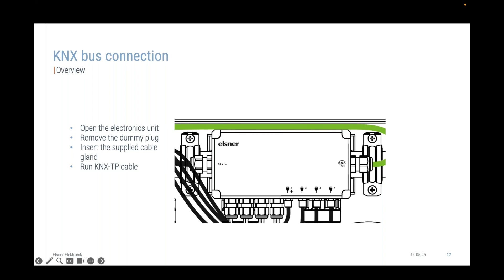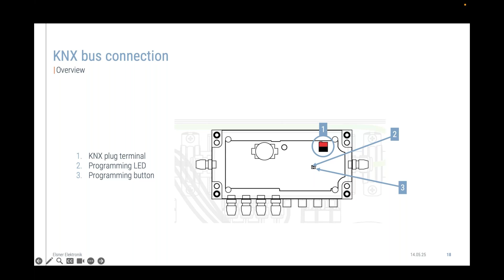This is where the KNX cable is connected to the KNX terminal, shown as number 1. You will also find the KNX button for assigning the physical address. It is not possible to supply the electronics of the Jardana with the 24 auxiliary voltage from the bus, since the magnetic valves require 24-volt alternating voltage.